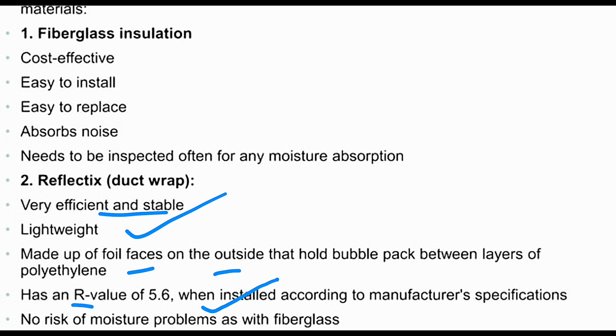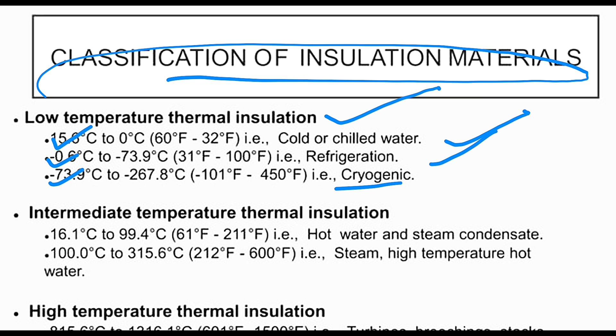Okay. So this is the classification of insulation materials. Low temperature thermal insulation: 15.6 degrees to 0 degrees Celsius, okay, cold or chilled water, and minus 0.6 degrees Celsius to minus 73.9 degrees Celsius is the refrigeration. Next is minus 73.9 degrees Celsius to minus 267.8 degrees Celsius, the cryogenic.